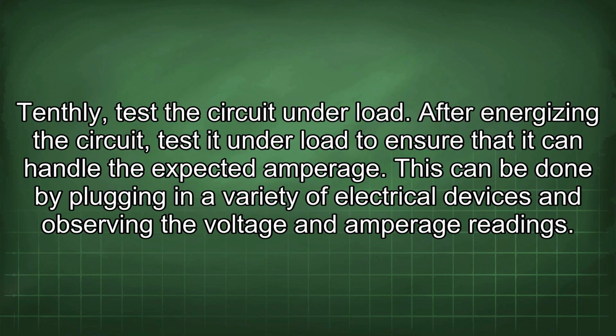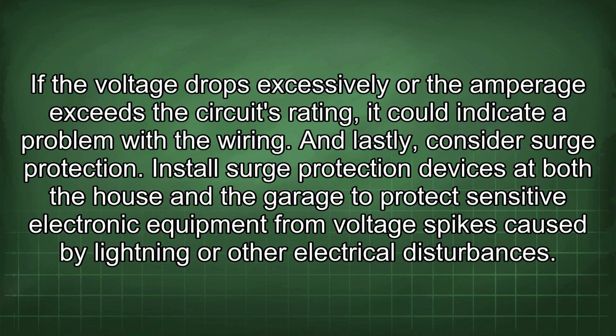After energizing the circuit, test it under load to ensure that it can handle the expected amperage. This can be done by plugging in a variety of electrical devices and observing the voltage and amperage readings. If the voltage drops excessively or the amperage exceeds the circuit's rating, it could indicate a problem with the wiring. And lastly, consider surge protection.